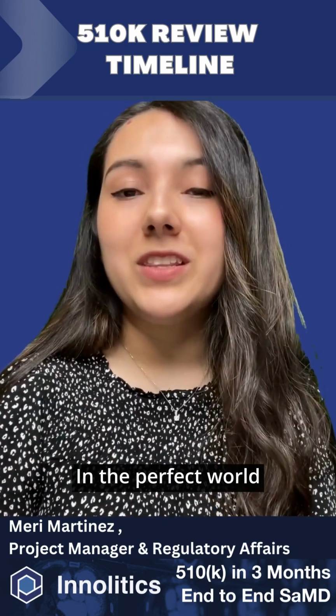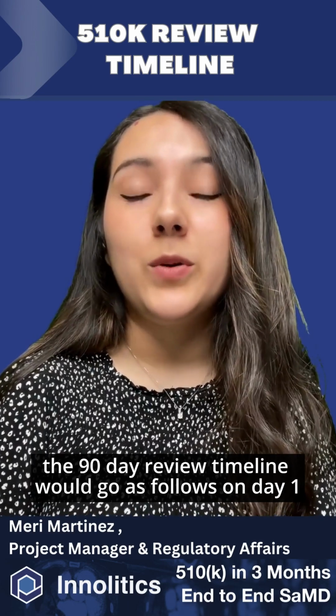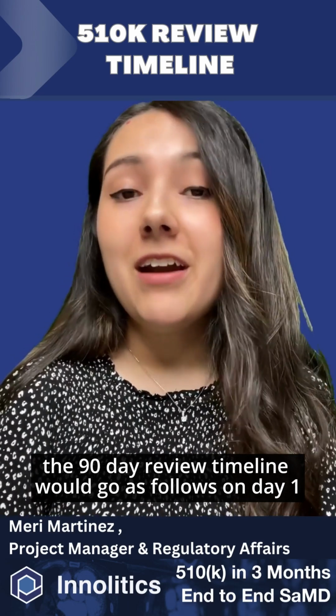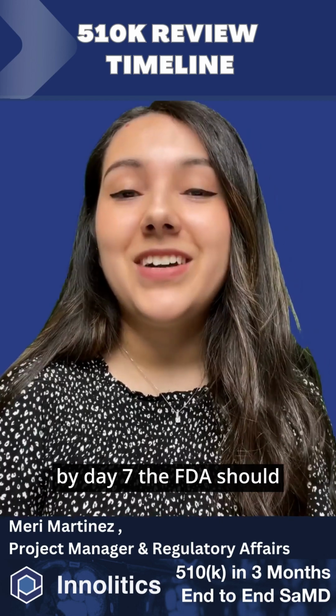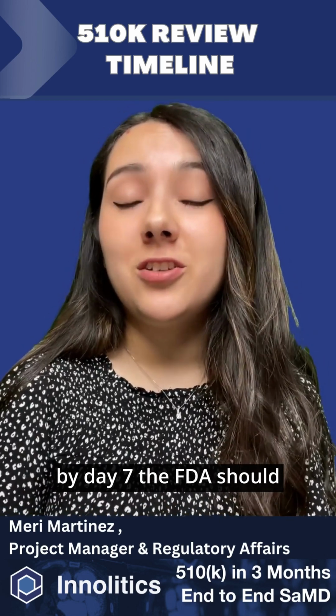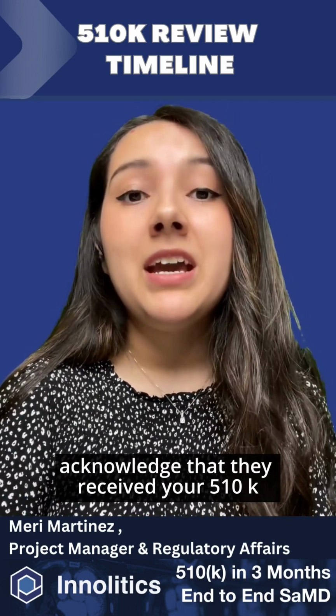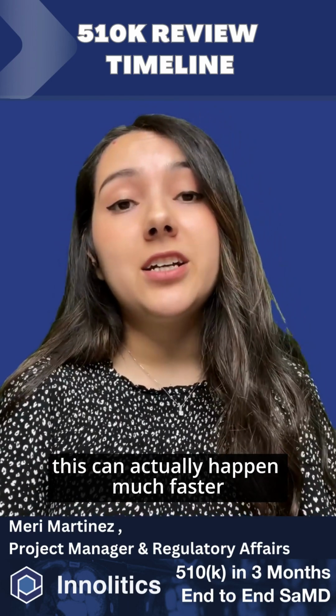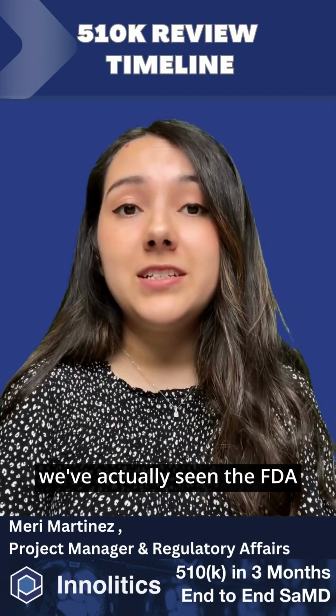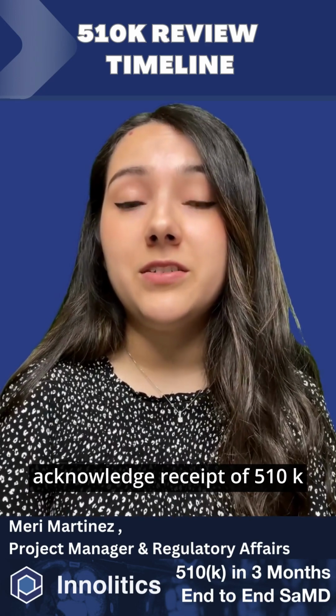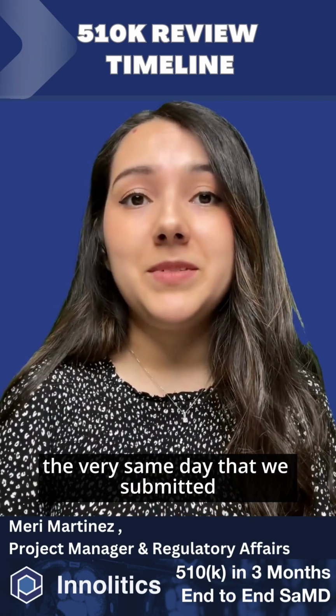In the perfect world, the 90-day review timeline would go as follows. On day 1, FDA receives your 510(k). By day 7, the FDA should acknowledge that they received your 510(k). Now, please note that with eSTAR, this can actually happen much faster. We've actually seen the FDA acknowledge receipt of a 510(k) the very same day that we submitted.